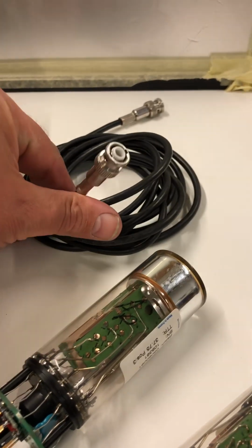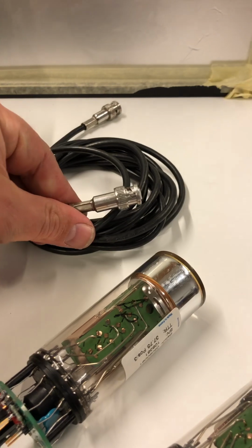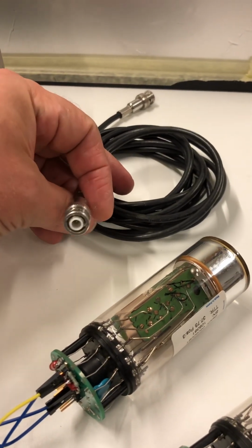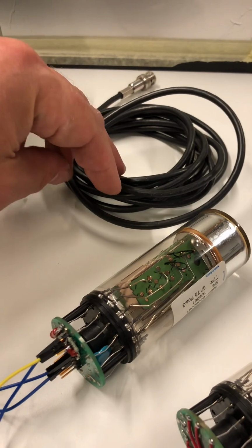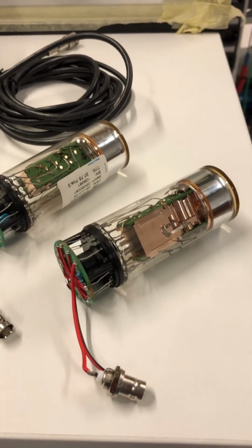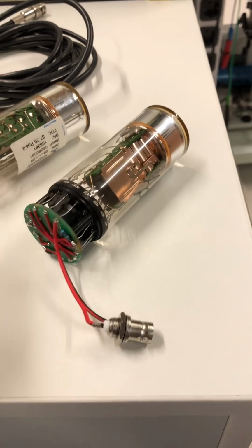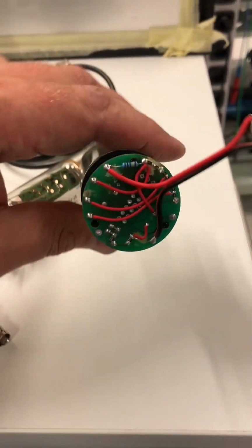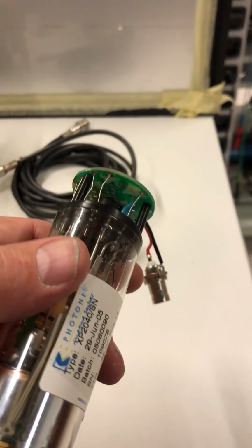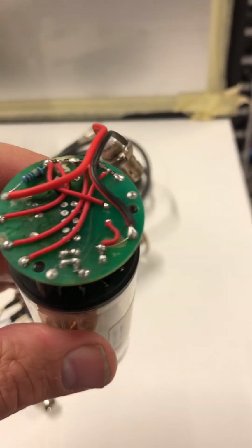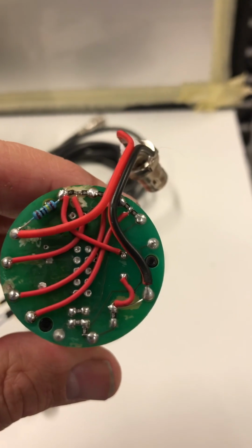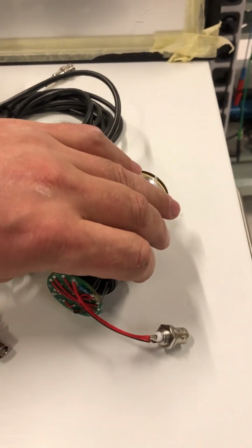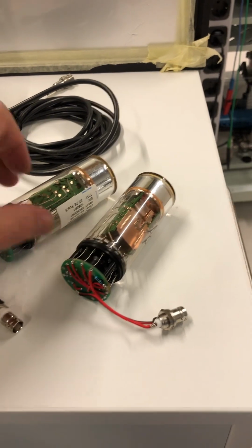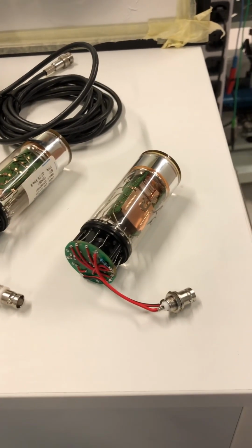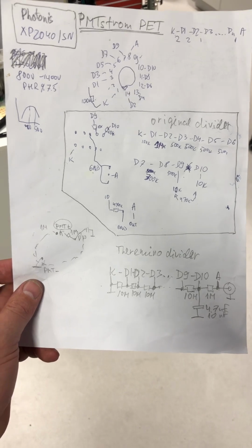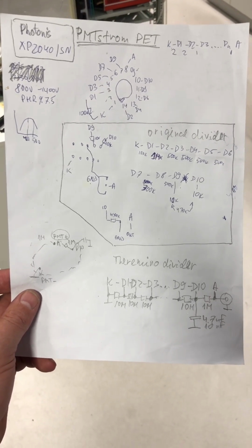For high voltage, there are high voltage cables and connectors, which look like BNC, but they are for 3 to 5 kilovolts. And then I removed the resistors with hot air and a Dremel mill, and soldered the divider with 10 megaohm resistors. And now the PMT is good for the Theremino driver. Here is a schematic of the original PMT and the one modified for Theremino.